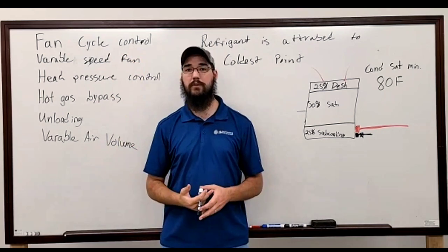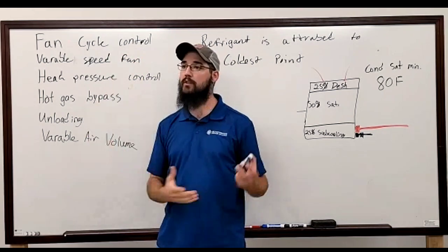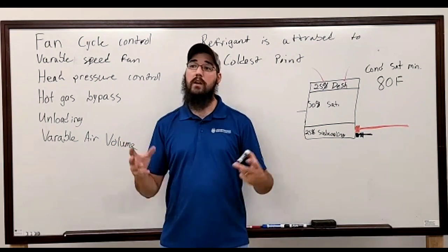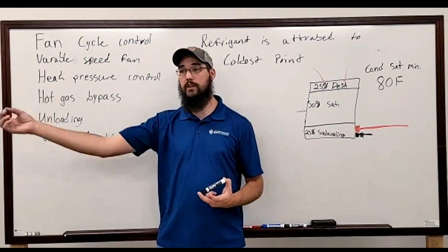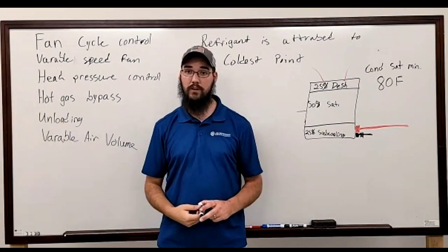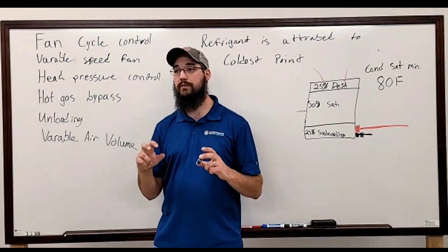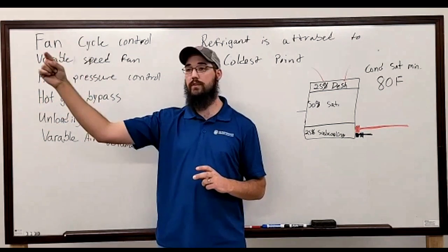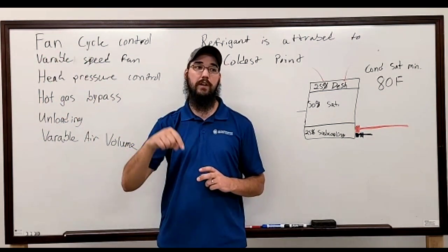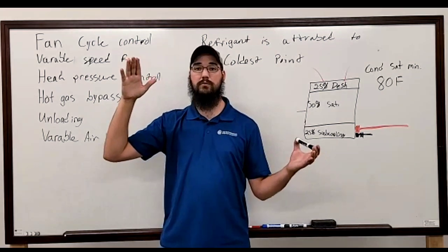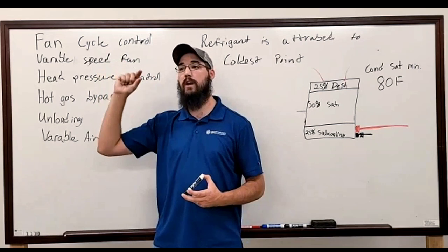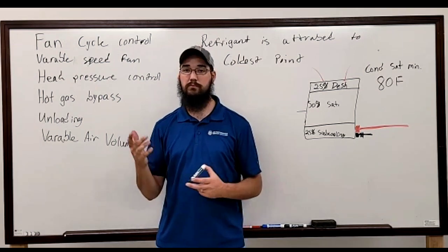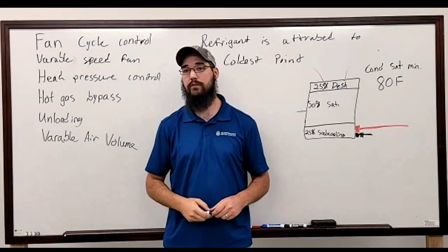At that point, we're operating like a regular VFD. All the same principles apply, all the same troubleshooting applies. It's a VFD, it needs a control signal reference. Some of those drives will actually look at the transducer directly. An example of that is Carrier, their Motormaster VFDs. You'll run the transducer directly to the VFD, not through the system controls. Then it will convert a 0 to 5 volt signal to a head pressure and ramp its fan speed based off of that head pressure. So there are some condenser fan drives that function that way.